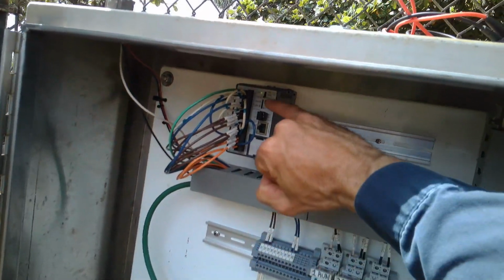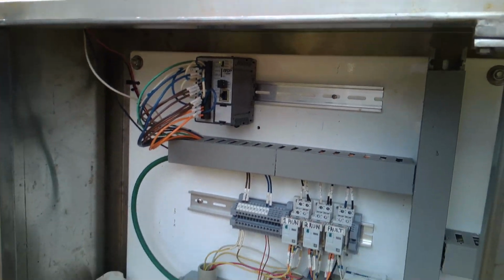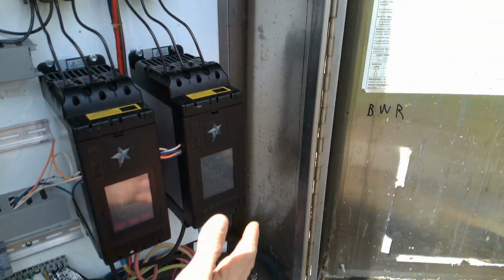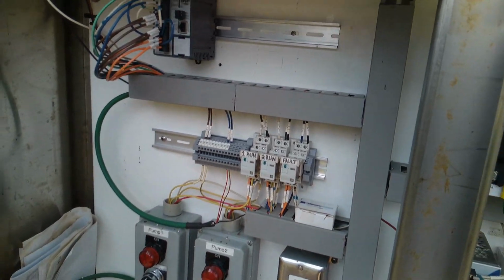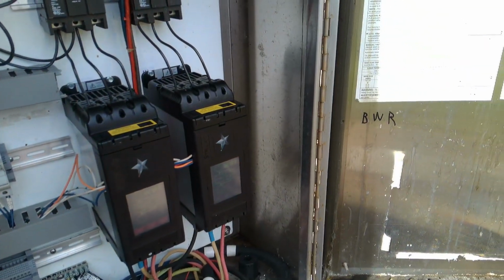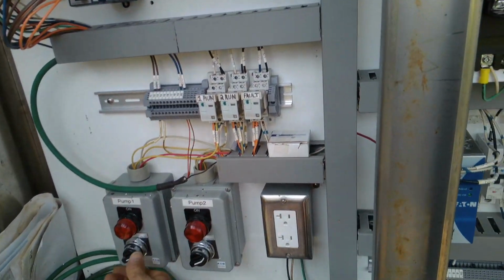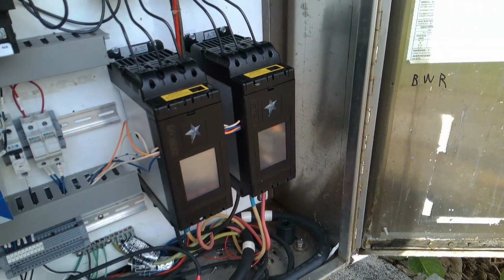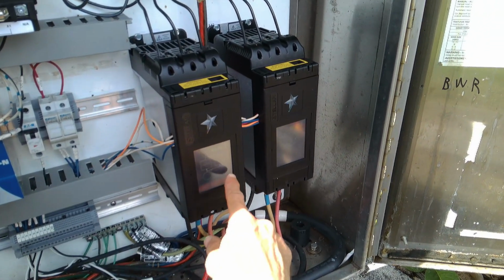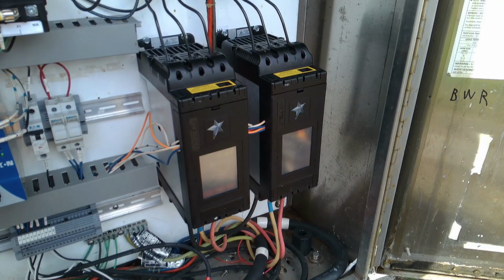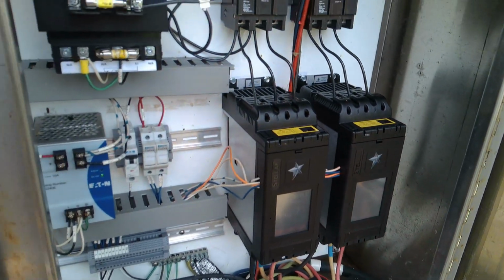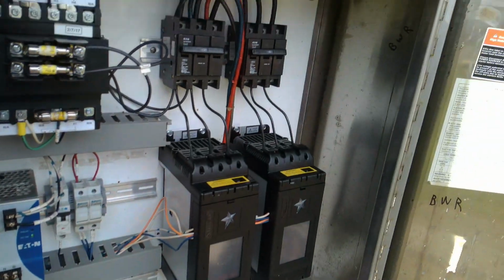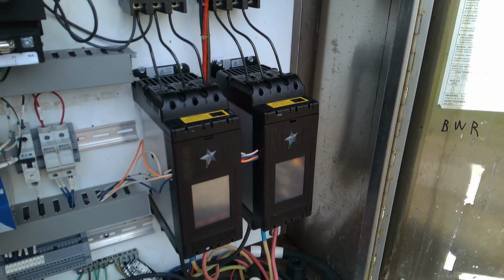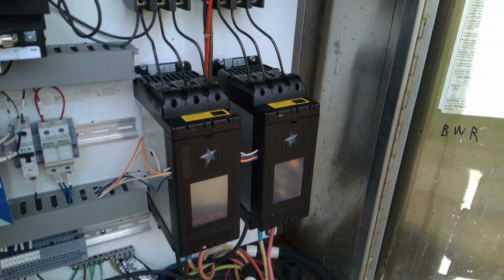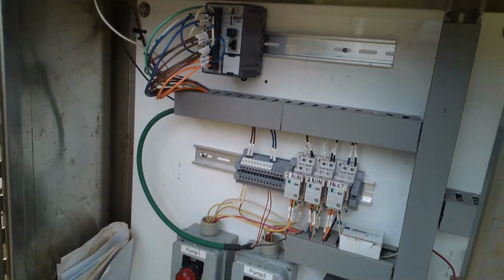Okay, so see how the run light is not lit? That means the PLC is not going to do anything. It's not going to call for anything. If we put these in auto, nothing should happen. I wonder if they'll even run in hand. They will run in hand. There goes 33 amps, 36. Yep, it's running. Good. Turn that off. There, it's ramping down. So hand works. That's a start.